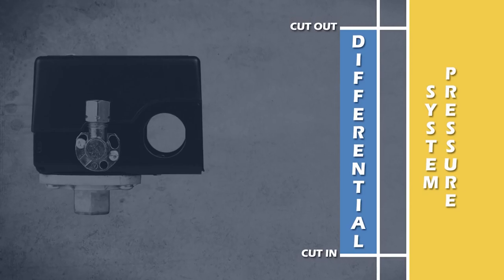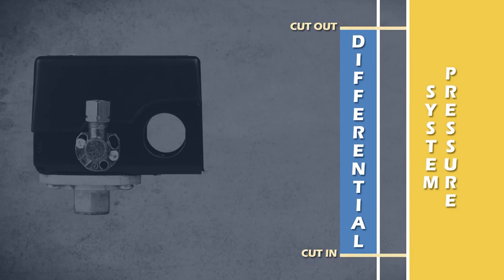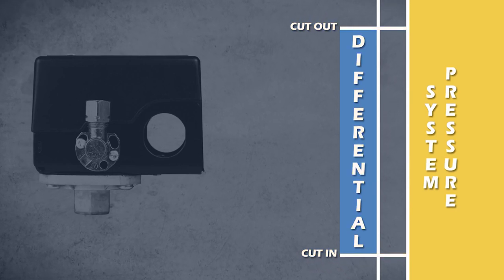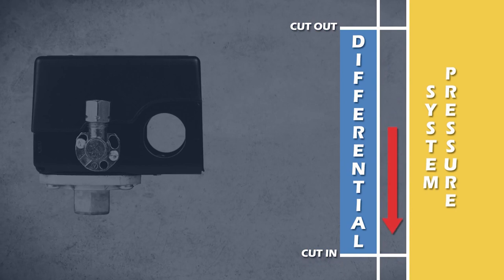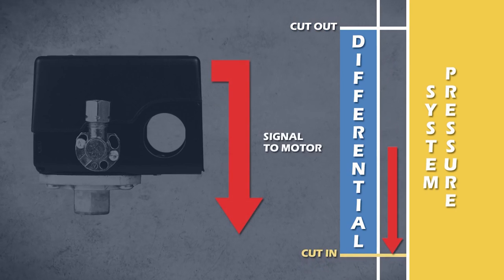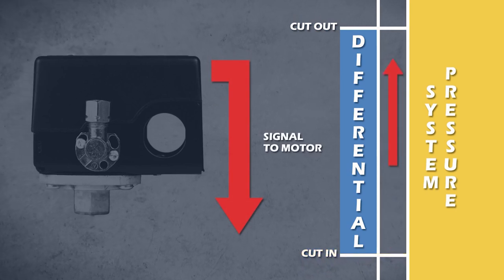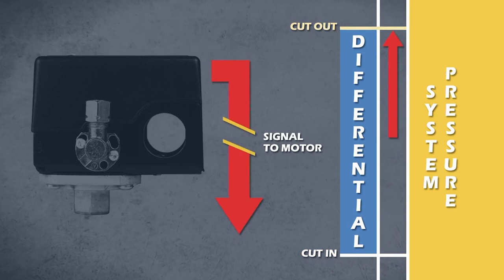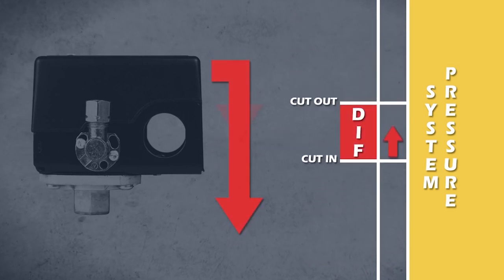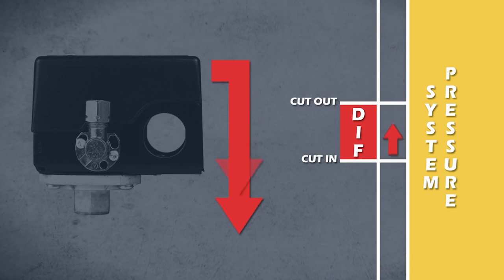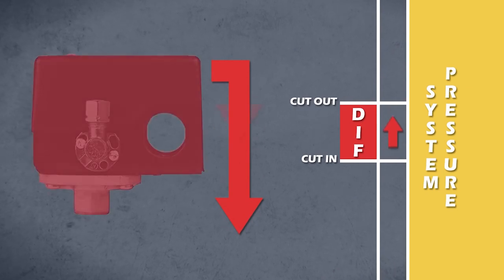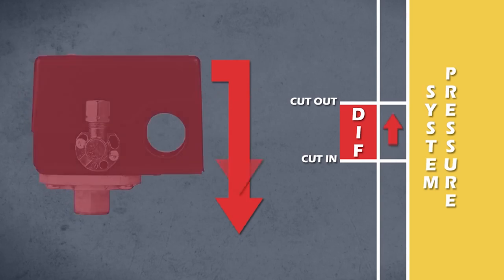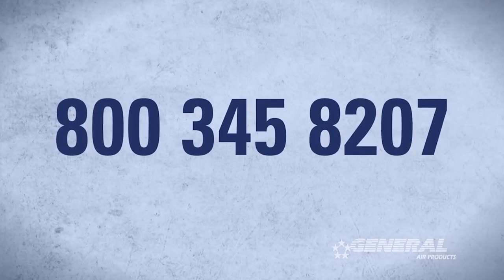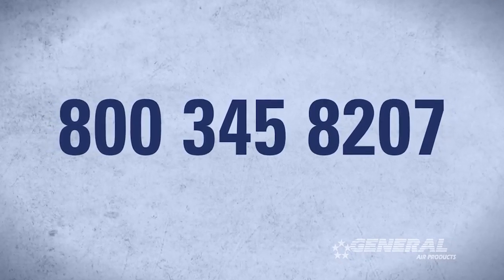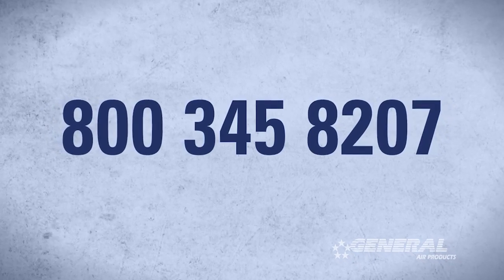Allow me to explain. When we talk about adjusting the pressure on a pressure switch, we're adjusting the cut-in and cut-out pressures simultaneously while leaving the differential pressure unaffected. When the cut-in pressure is reached, the switch sends a signal to the motor to run. When the cut-out pressure is reached, the switch sends a signal to the motor to turn off. When the differential pressure is adjusted incorrectly, these signals are sent too frequently, causing the pressure switch to fail or the compressor to short cycle itself to death.